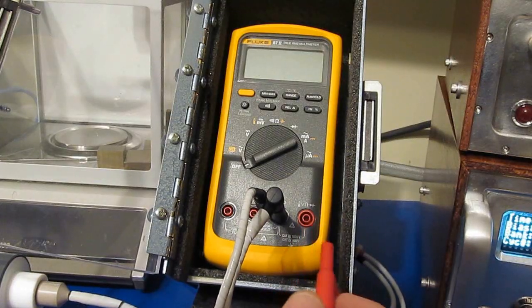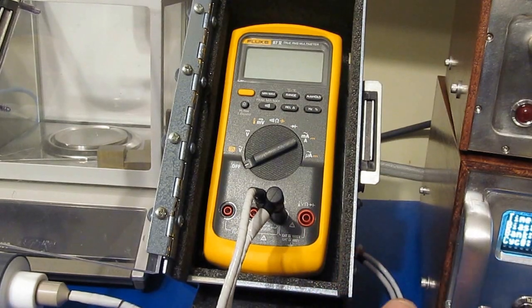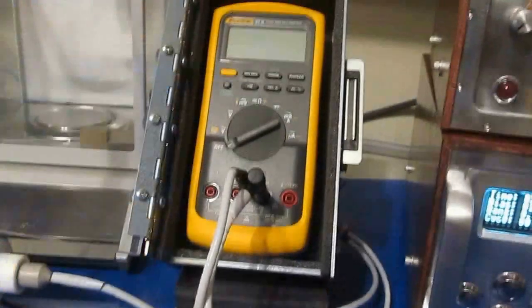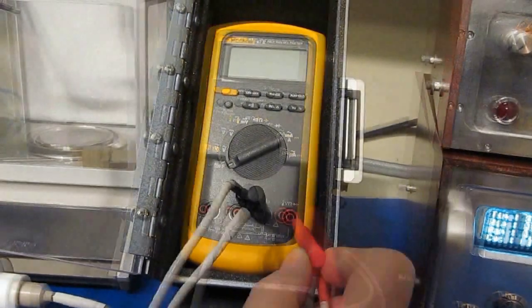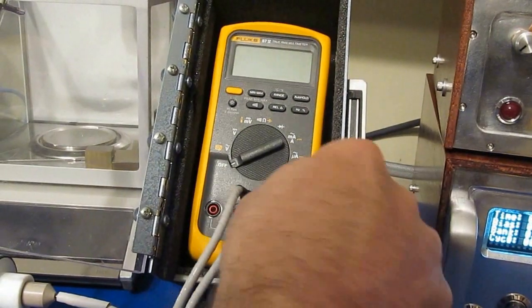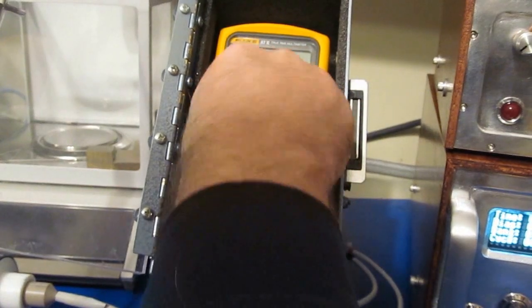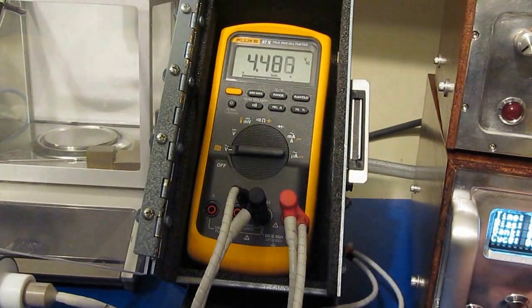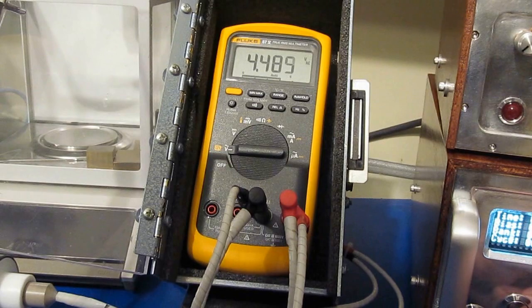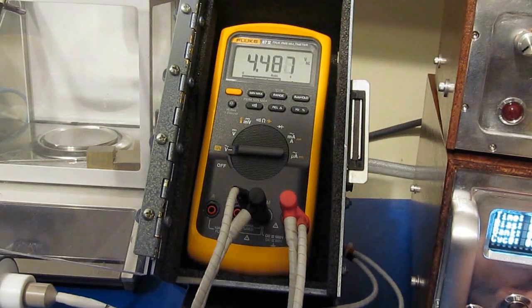So the next test I'm going to run - I've got the transient generator turned all the way up, just shy of 6,000 volts, and again we'll be running both positive and negative pulses, doing this with the meter set to each mode. So again, this will be 5 transients, about 5,800 volts peak with a 2 ohm source impedance.